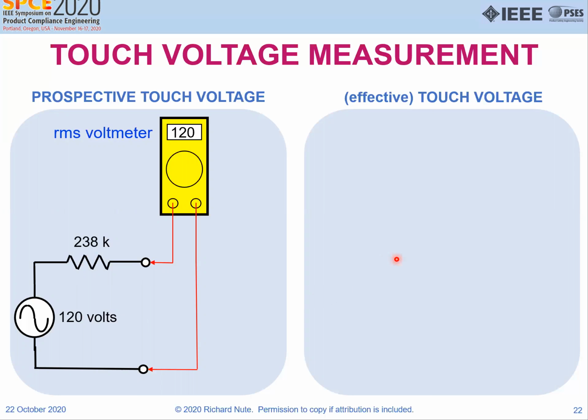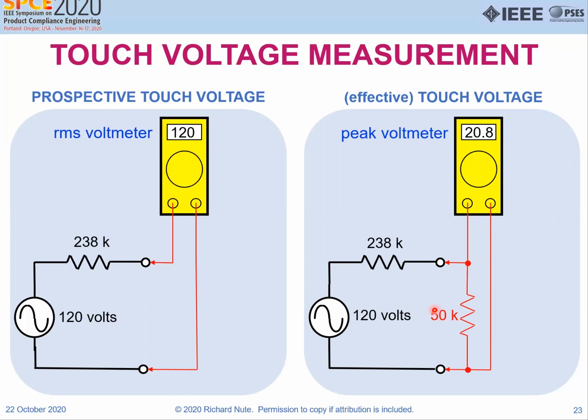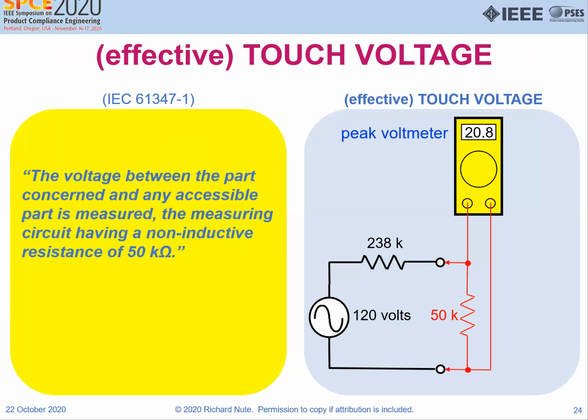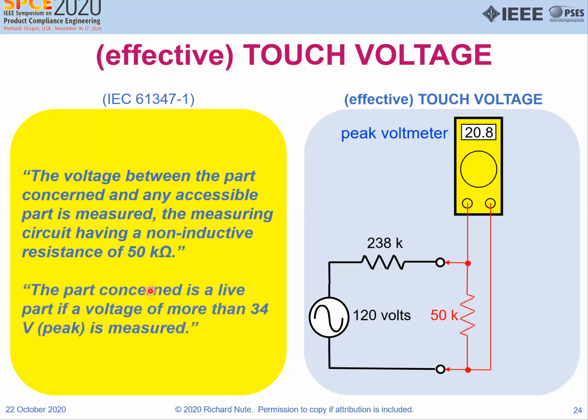But if you look at effective touch voltage, you put a 50K resistor across the same thing, and you measure peak voltage as 20.8 volts. So that's still effective, that's low voltage. The voltage between the part concerned and the accessible part is measured, the measuring circuit having a non-inductive resistance of 50,000 ohms. The part is concerned as a live part if the voltage is more than 34 volts peak.